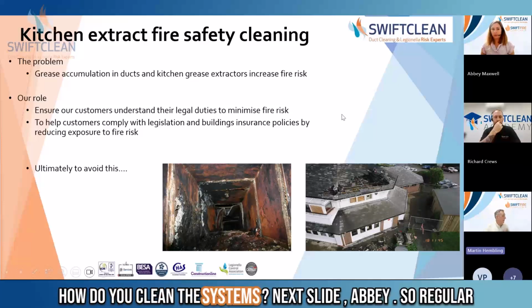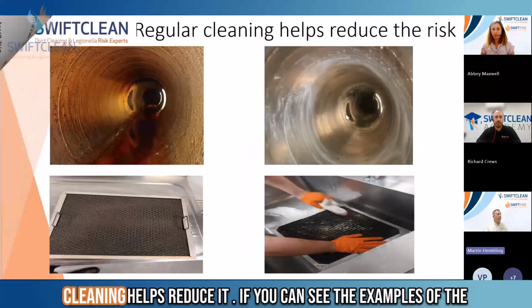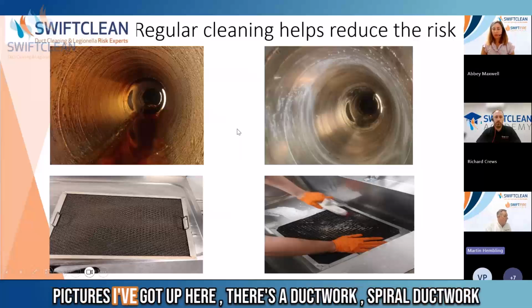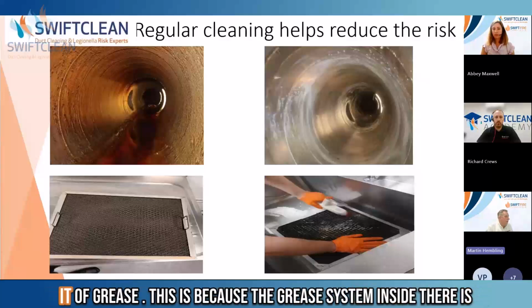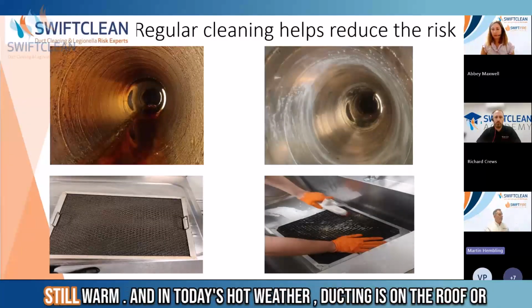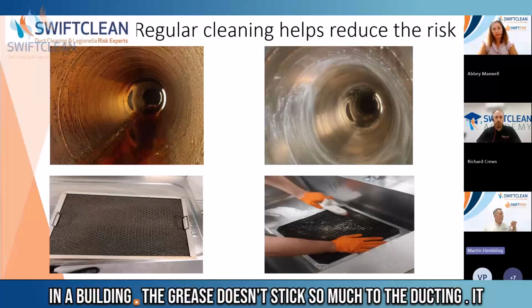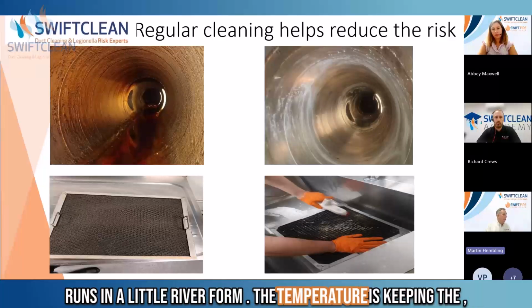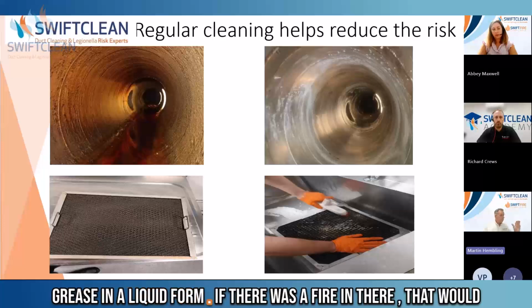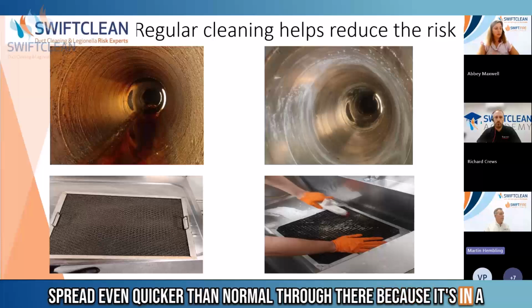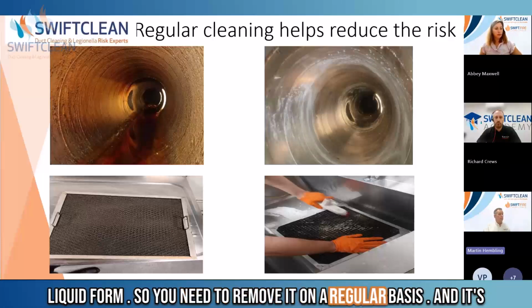How do you clean the systems? Regular cleaning helps reduce it. You can see the examples in the pictures I've got up here - there's spiral ductwork with grease that looks like it's got a little lake running through it. This is because the grease inside is still warm, and in today's hot weather, ducting on the roof or in a building, the grease doesn't stick so much, it runs in a little river form - the temperature is keeping the grease in a liquid form. If there was a fire in there, it would spread even quicker than normal because it's in a liquid form.